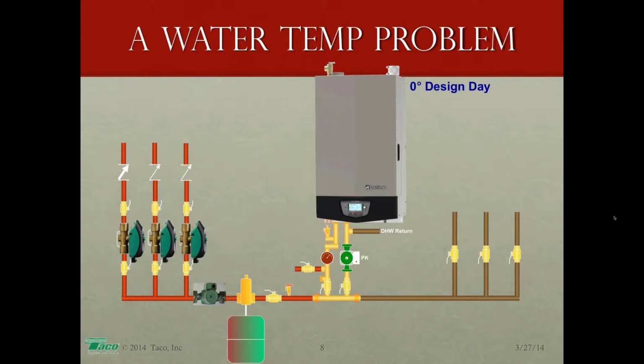If I'm understanding your question, Julio, typically when we're talking about velocities, the pipe sizes are what they are because they have a minimum of 2 feet per second and a maximum of 4 feet per second. That's the minimum and maximum fluid velocities. Any more than 4 feet per second, you run the risk of velocity noise. Less than 2 feet per second, dissolved gases want to come out of solution and you have air issues. Another reason why we have that short fat header: the velocity slows down, and air bubbles will go up to the top and then go out an air vent. Doesn't necessarily replace an air separator, but it's a good thing to have.